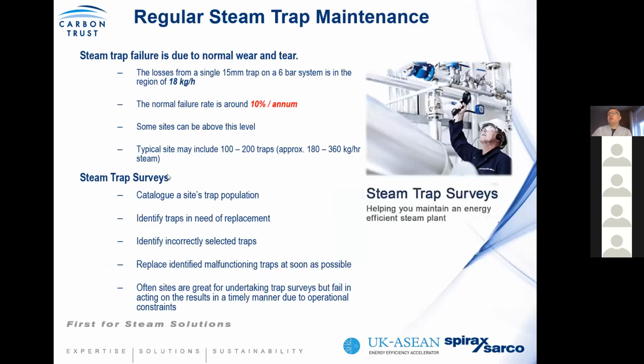So finally, we're just going to talk about steam trapping. When we mentioned the continuous assessment, what we need to understand is that a steam system requires continuous improvement. You should assess your steam trap population at least once per year, because if we take international best practice, your failure rate should be anywhere around 5 to 10%.